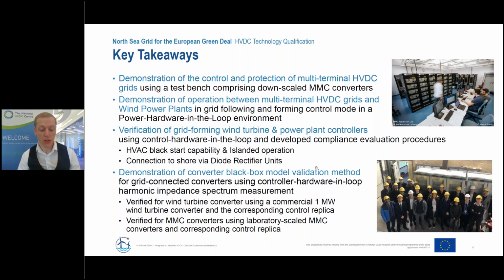We were able to verify grid forming wind turbine and power plant controllers using control hardware in the loop, and develop compliance and evaluation procedures for high voltage AC, black start and island operation, and also the connection to shore via diode rectifier units. This was done with multiple academic wind turbine controllers implemented on physical hardware, as well as a manufacturer supplied wind turbine generator controller, which was tested at DNV-GL.